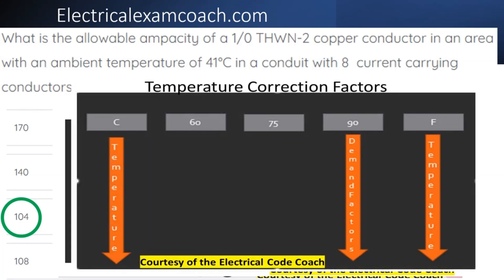Then we're going to head over to our temperature correction factor table. We start on the left-hand side because the temperature is in Celsius. We come down to find our temperature, but we have to be sure to cross all the way back over to the 90 degrees C column to actually get the correction factor.